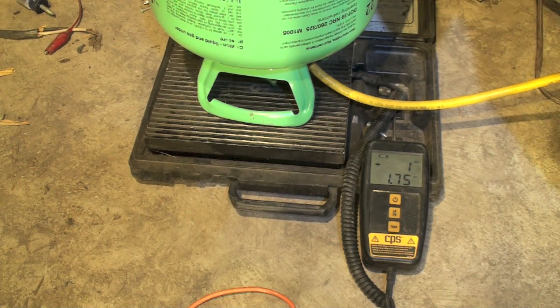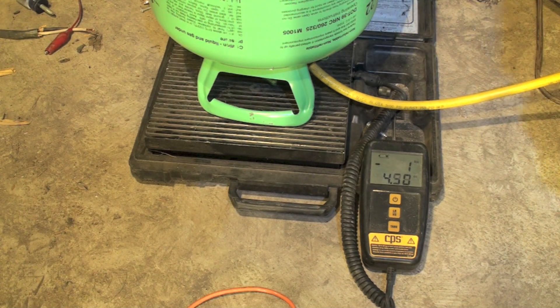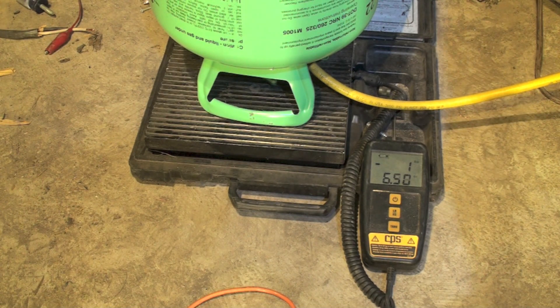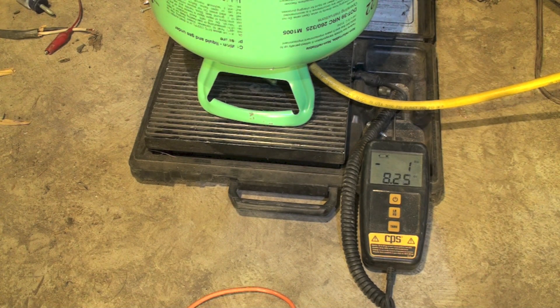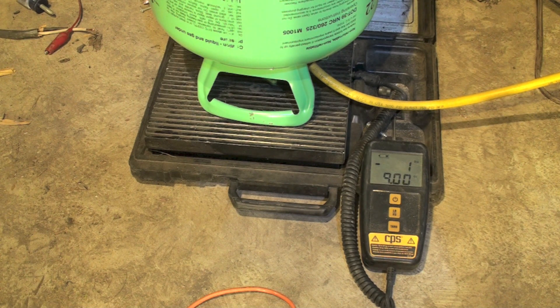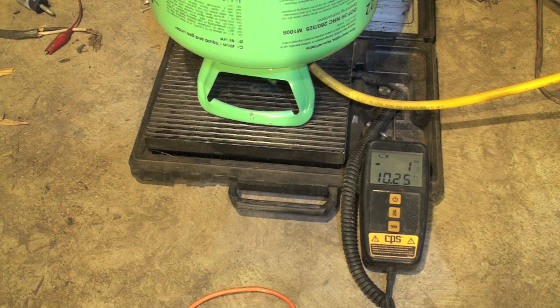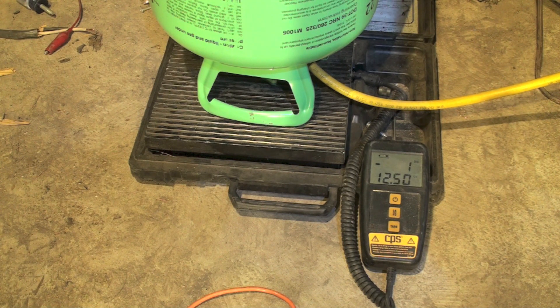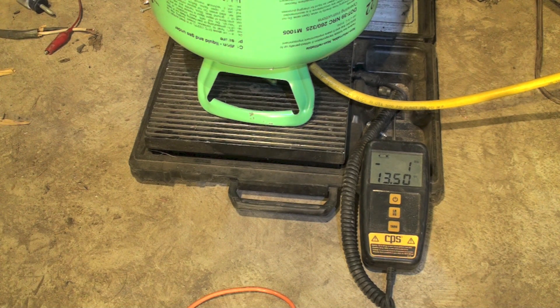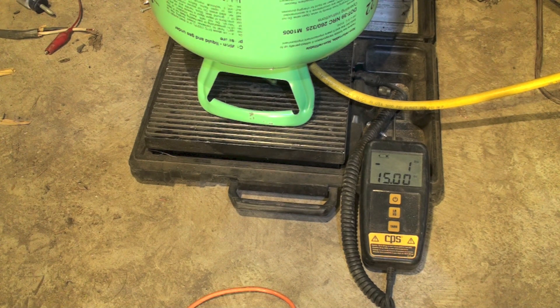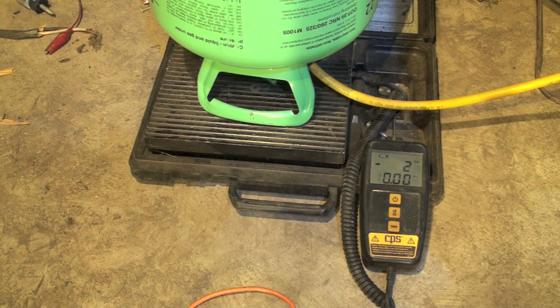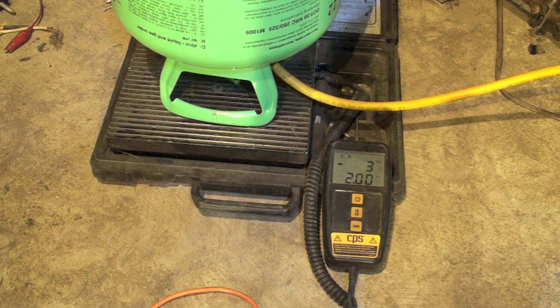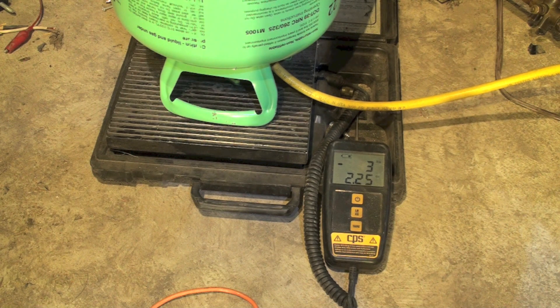Now these almost never put in the entire charge on liquid. It usually equalizes out the pressures before we get it full, but you never know for sure. I've had them go over. This one doesn't look like it's going to go over. It's taking quite a while to get anything in. We'll just sit there and watch that. We're up to a little better than three pounds.